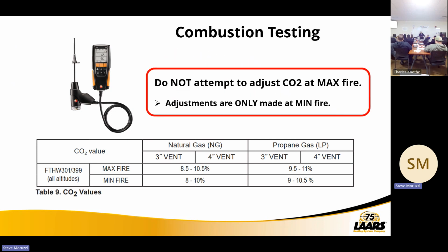Do not attempt to adjust CO2 at full fire. So these products that we've talked about here today, you only adjust CO2 at low fire. So if I go to high fire, and let's say I'm running at 10.7% CO2, I obviously have to lower that, right? So check high fire first. Am I within range or am I out of range? Now go to low fire. Now, in this example, low fire needs 8 to 10. Well, maybe I'm only running at 8.5 or 9 in low. I still have room for adjustment. Does that make sense?